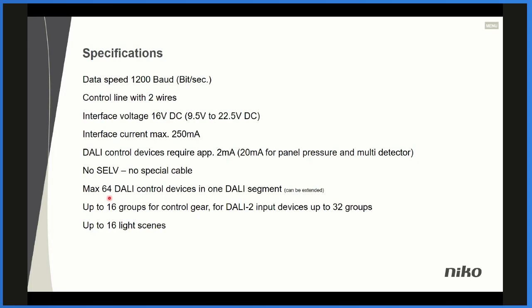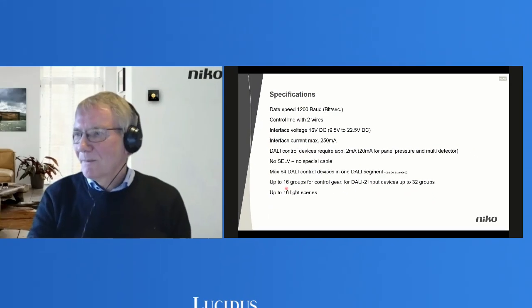There are 6 bits in combination, and that means a total of 64 different addresses that we can have on one DALI bus. It can be extended in certain special occasions. The number of groups is limited to 16, and that means you can have up to 16 different lighting controls on the DALI bus. With DALI 2 input, it's up to 32 groups. And the light scenes are a maximum of 16.